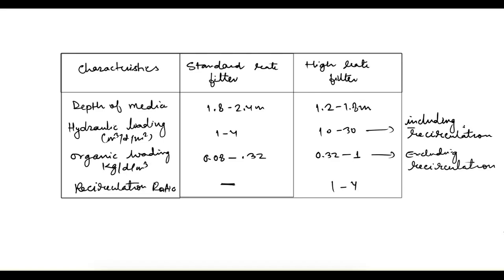In this video we will see example problems related to trickling filter design. First, let's look at some design data comparing standard rate and high rate filters. The depth of media is between 1.8 to 2.4 meters for standard rate filters, and 1.2 to 1.8 meters for high rate filters. So in case of high rate filters, we can take a smaller depth of media.